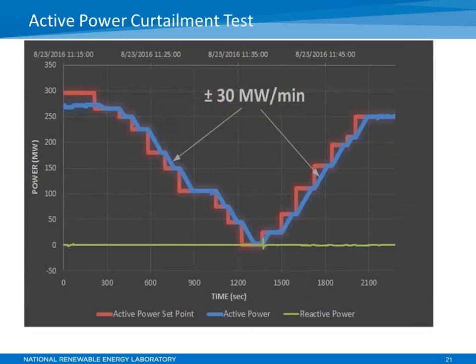So this particular test shows the curtailment control of this plant with a particular ramp rate. In this case, we utilize a 30 megawatt per minute ramp rate capability. So the PV plant under test is capable of deploying all 300 megawatts of its spinning reserve in only 10 minutes. Well, assuming some hypothetical case of full curtailment, of course.